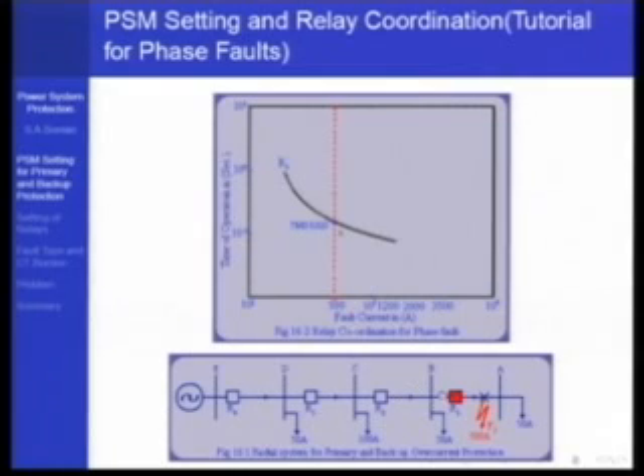First of all, if you notice the way overcurrent characteristics are, they tend to come closer when the fault currents are high, and when the PSM is low, they tend to diverge a bit. So they are not exactly running parallel to each other. When you increase the TSM, you don't see that they are running exactly parallel. They tend to converge at higher fault currents, that is when the PSM is high, and they tend to automatically diverge when the PSM is low.